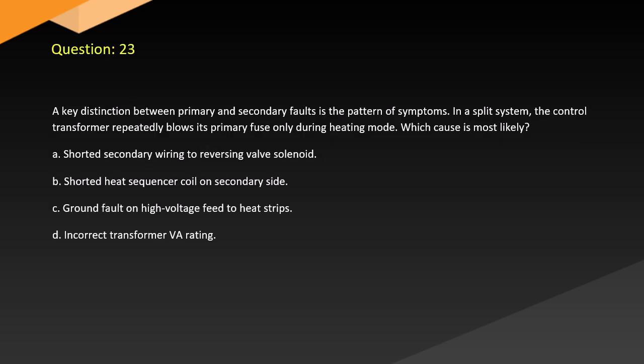Question 23. A key distinction between primary and secondary faults is the pattern of symptoms. In a split system, the control transformer repeatedly blows its primary fuse only during heating mode. Which cause is most likely? A. Shorted secondary wiring to reversing valve solenoid. B. Shorted heat sequencer coil on secondary side. C. Ground fault on high-voltage feeder to heat strips. D. Incorrect transformer VA rating.